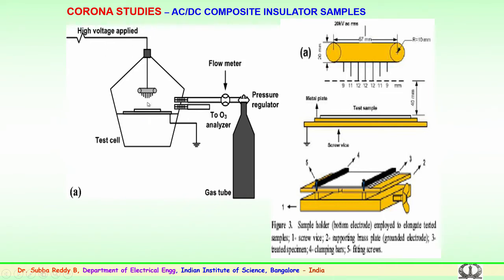The corona discharges from the needles will be impinged on the sample here, and the performance will be verified while supplying dry air or moisture, or an acidic effect could be pumped into the chamber. The effect could be studied over a period of time, and the results analyzed to see how the sample performs. Here we could also measure the leakage currents flowing to the ground. This will also help us to see the performance of the sample.